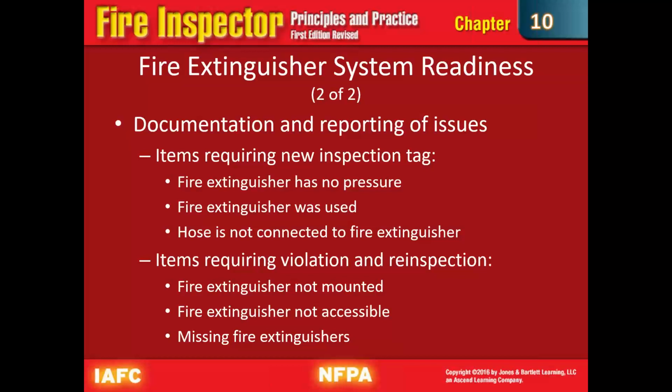Another thing, especially in our area, that we want to be aware of, whenever we're looking at fire extinguishers, especially your ABCs, and if they're mounted outside, you may have a dirt dauber that will build a little nest in there and it will block off that hose. That is some things that should be inspected during the annual inspection that whatever business has contracted to take care of their extinguishers. But I emphasize the word should. There's a lot of times where we find that they just went around and changed tags and didn't look at anything on them.